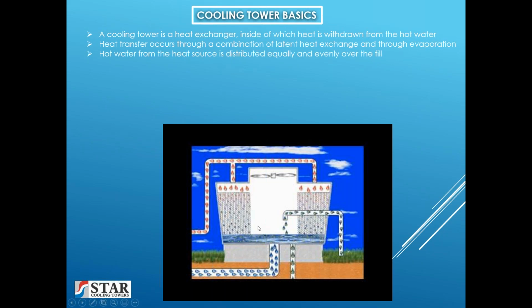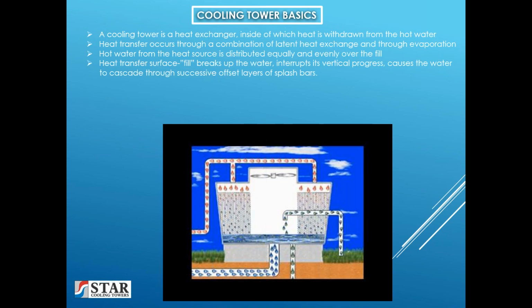Hot water from the heat source returns to the tower and is distributed evenly and equally through nozzles over the top layers of fill. The heat transfer surface, which we call fill, breaks up the water. It interrupts the vertical progress, causes the water to cascade through successive offset layers of splash bars.